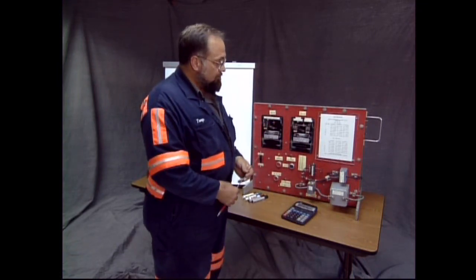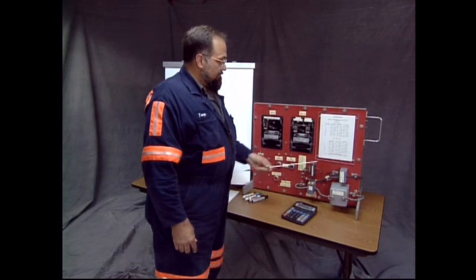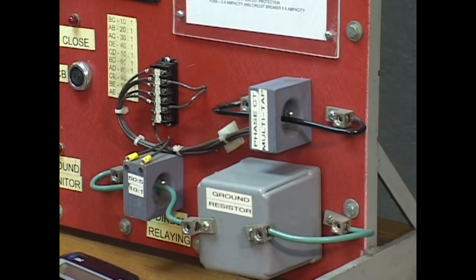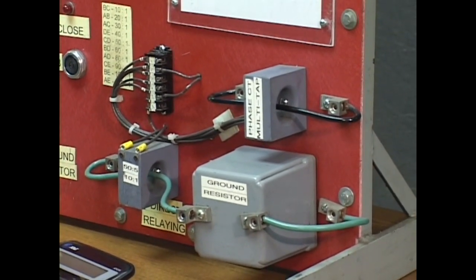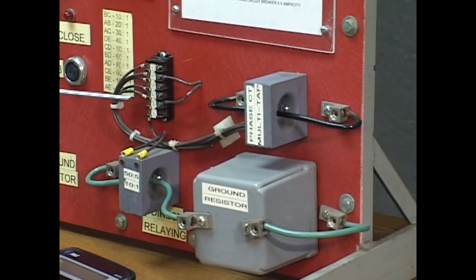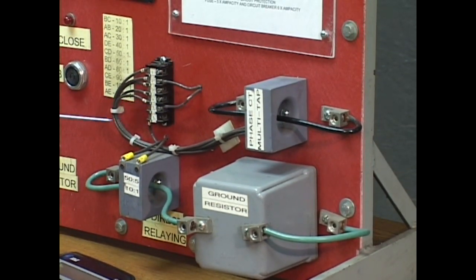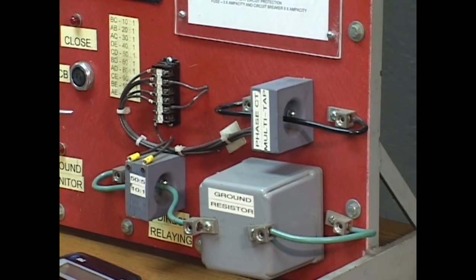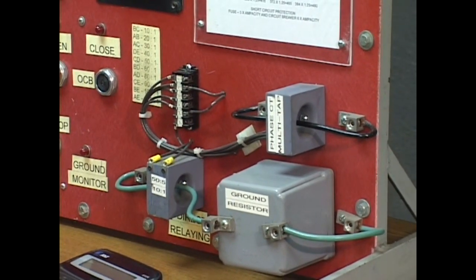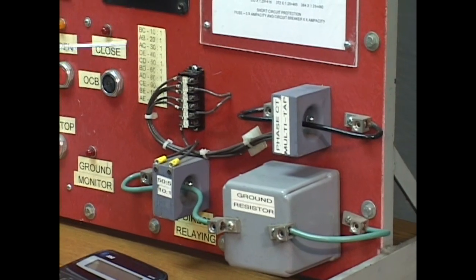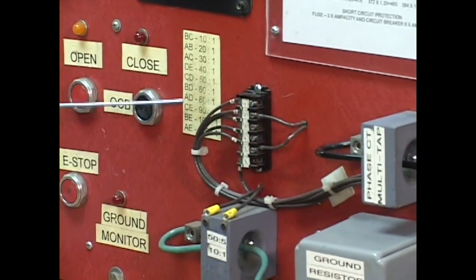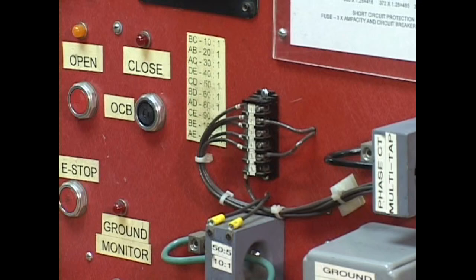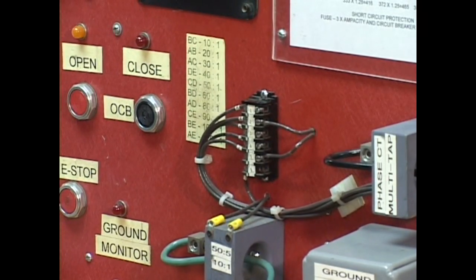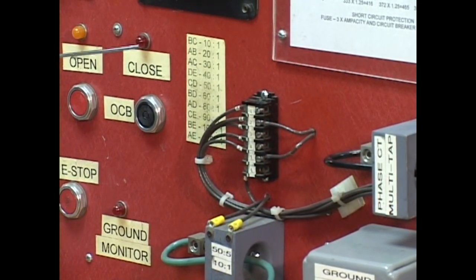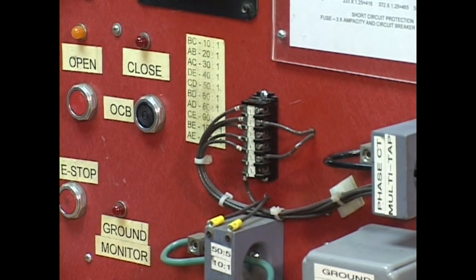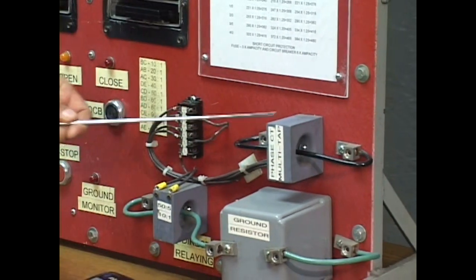Now, it's supplied by the phase CT. The phase CT is multi-tap. There's more than one ratio available to you here. These go from a 10-1 to a 120-1. You choose the letter of the leg wire to decide what ratio you're going to be using. And this is real similar to a real-life CT terminal block that you would find in a station. Phase CT has one phase in it.